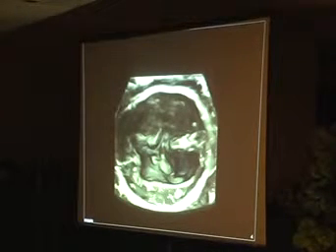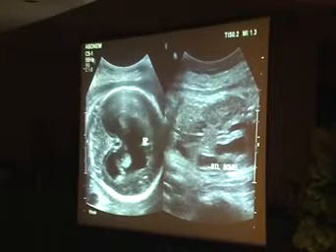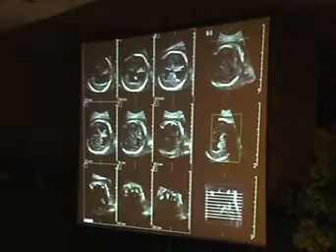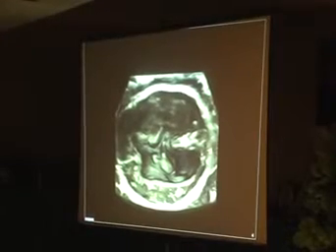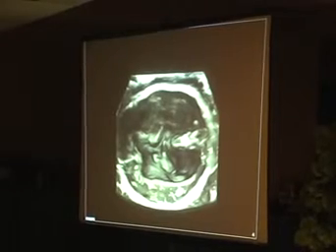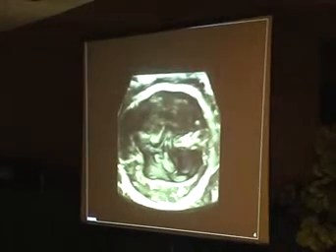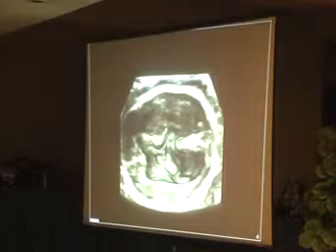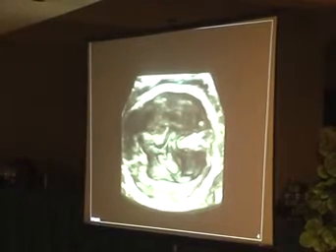Sir, I have a question. Is it taken with the normal probe, or the volume probe? No, not with the volume probe. The normal one. Yes, this 3D was taken with a normal 5-1 probe. There is a freehand 3D utility with every probe. Even the 2D probe can be used as a 3D probe, which is another innovation in Philips.